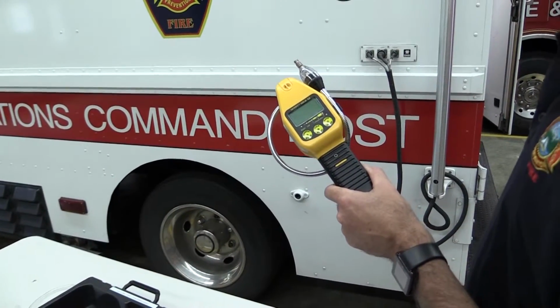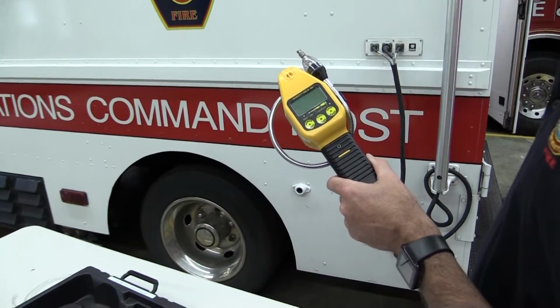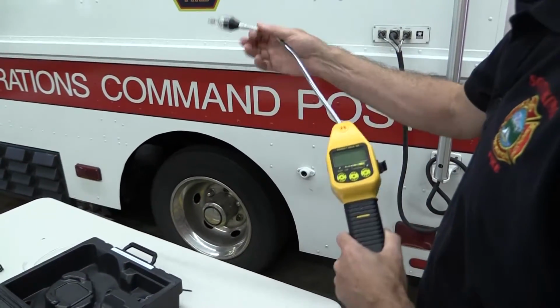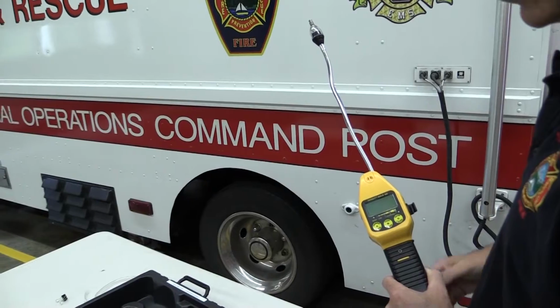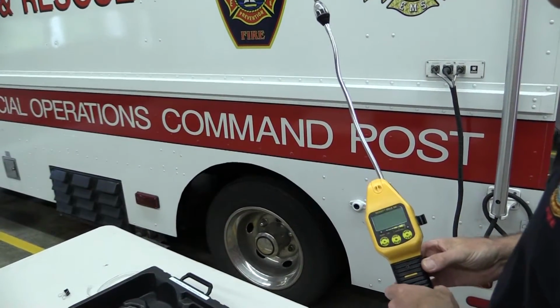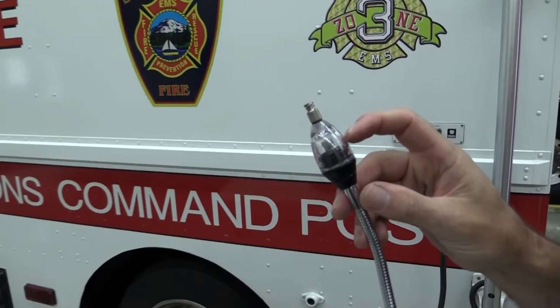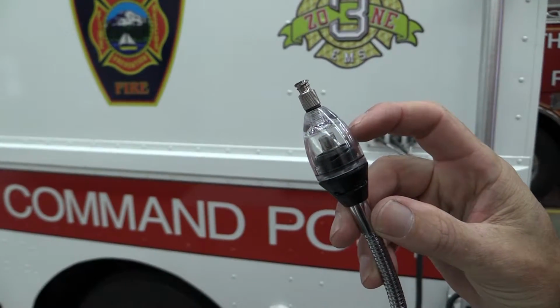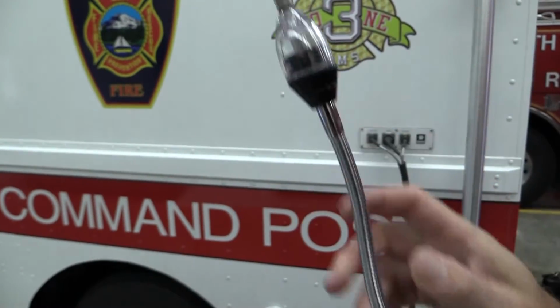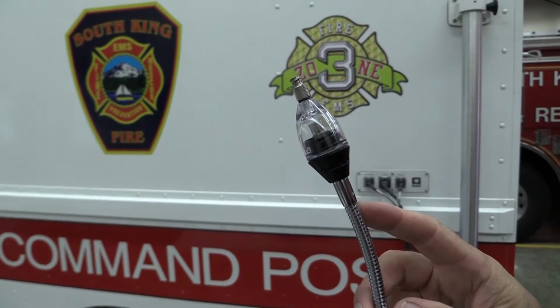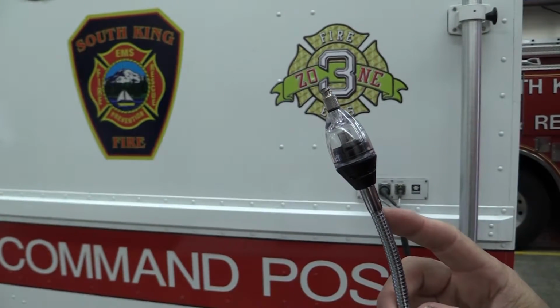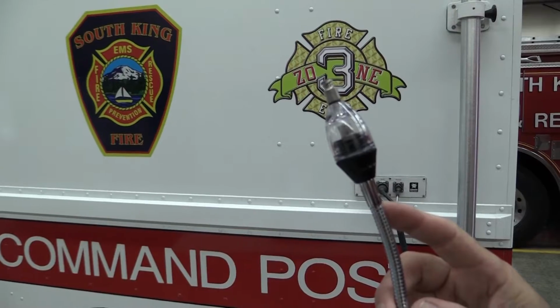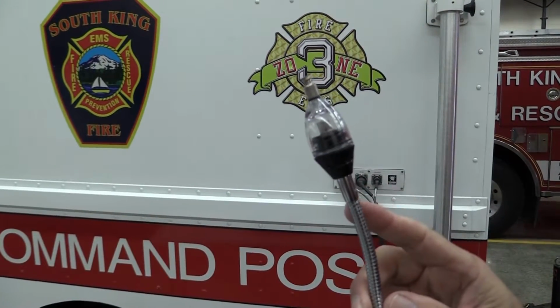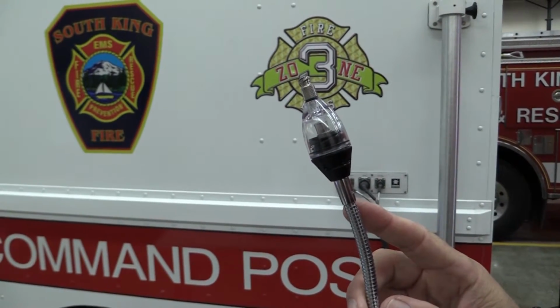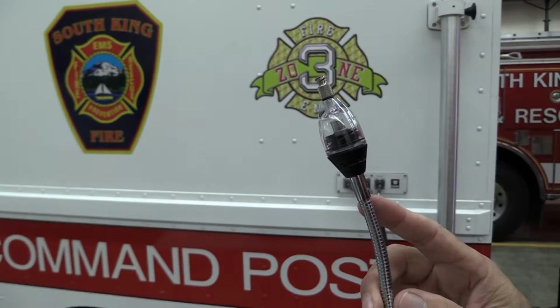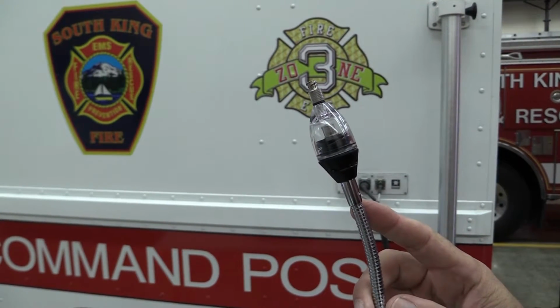The wand can be used in its stowed position like this, or extended as needed for your use. Note that unlike our multi-gas meters, the sensor for this unit is actually in the tip of the wand covered by this plastic cap, rather than being inside the unit. This configuration makes the unit much faster to respond to the presence of a gas than our multi-gas units. However, it also makes the sensor more vulnerable to damage. Use great care not to bang the probe head into things and to keep it out of liquids.